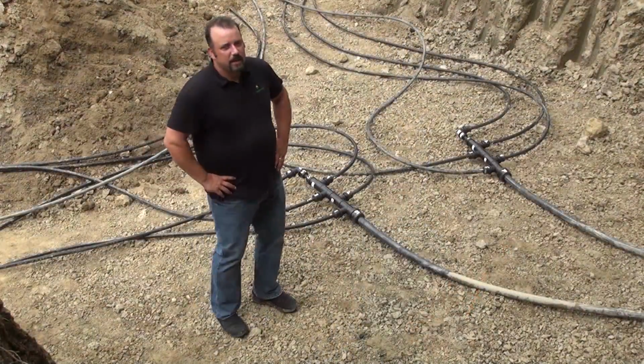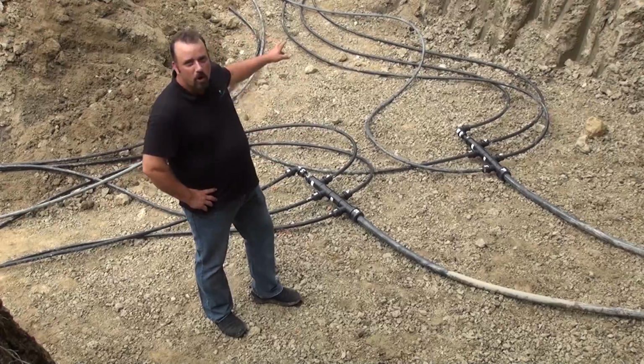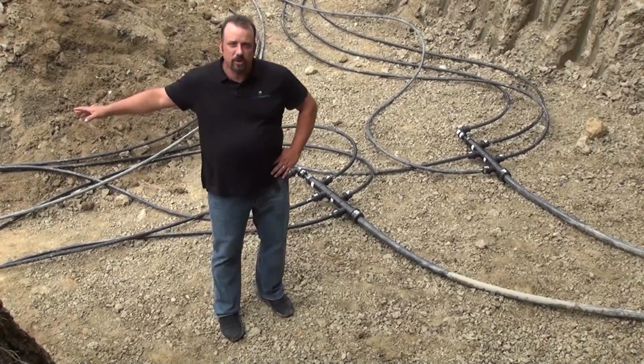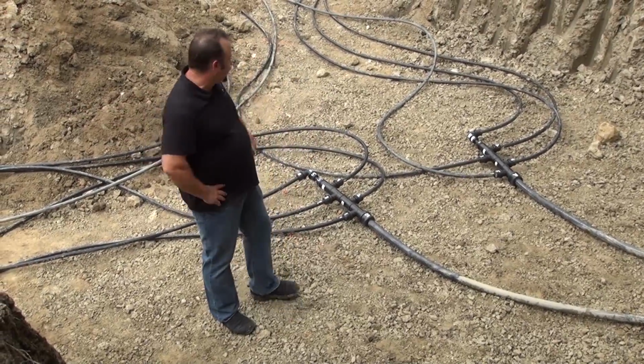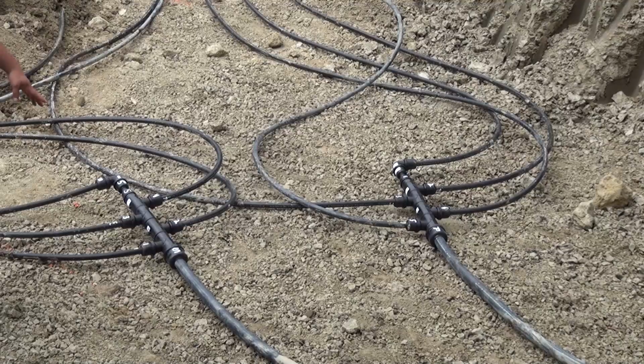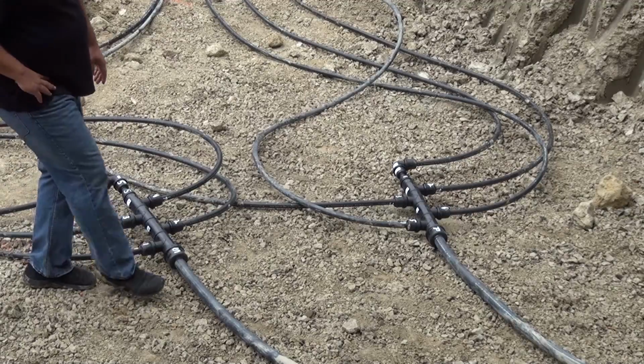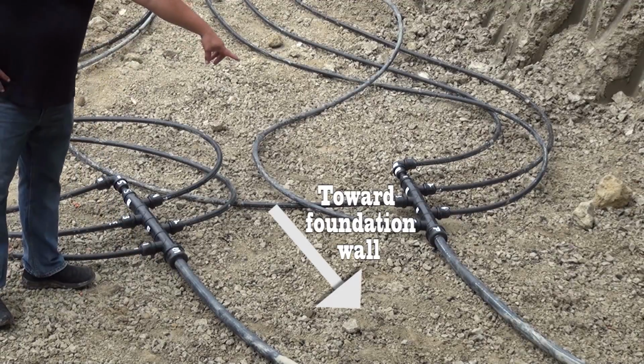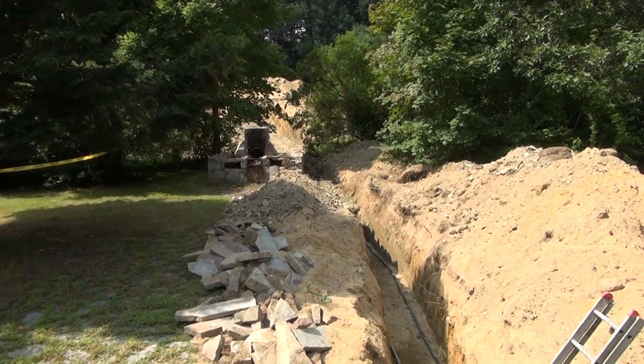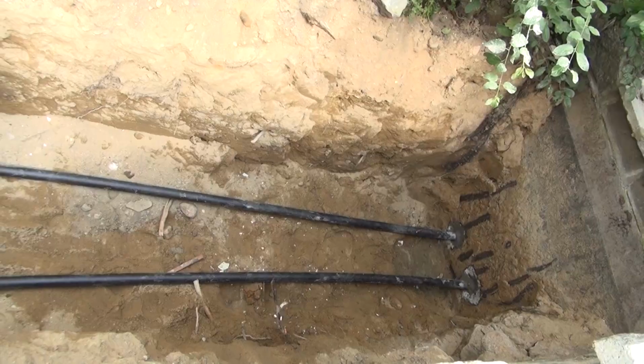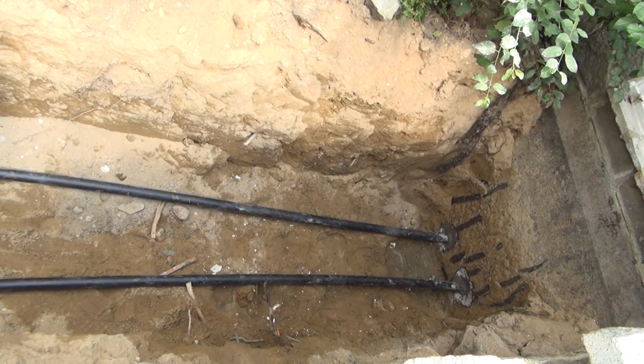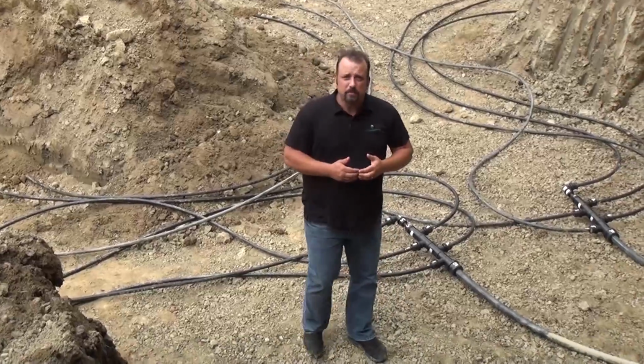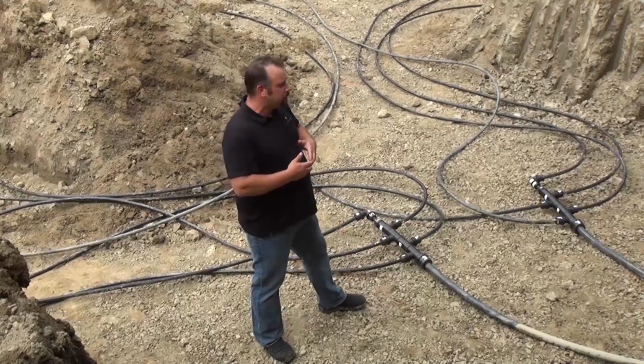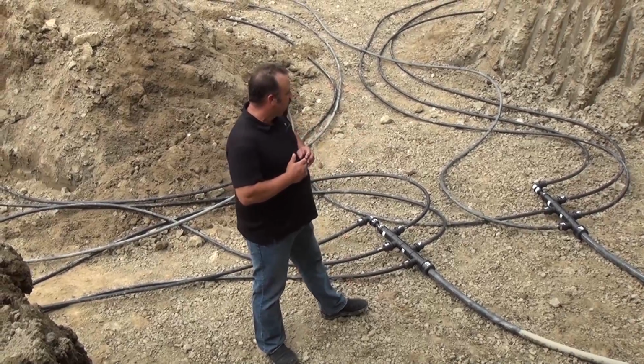Here we are at the manifold entrance, where all of the loops that come from this horizontal field enter into what we call a two-pipe reverse return manifold. So basically, you'll see that this is a supply pipe, and this one over here is a return pipe. Both of these pipes go through this offset trench and into the basement of the house, where they will be connected to a circulator module system that'll tie into the heat pump and circulate through these loops.